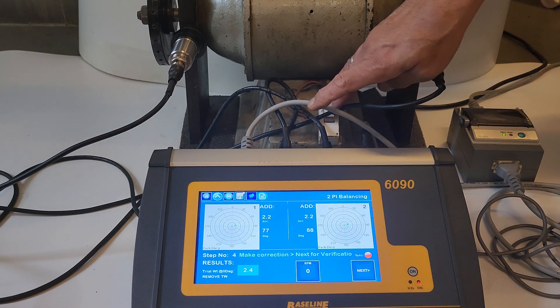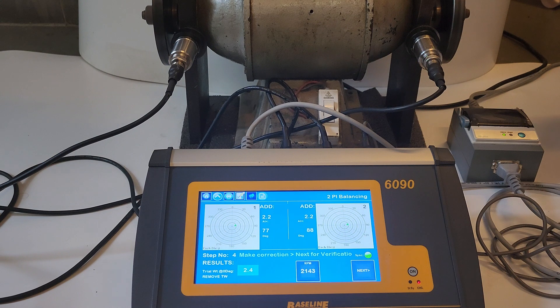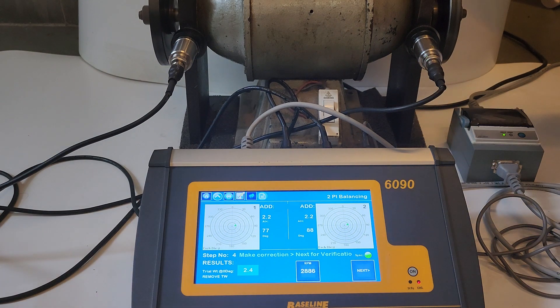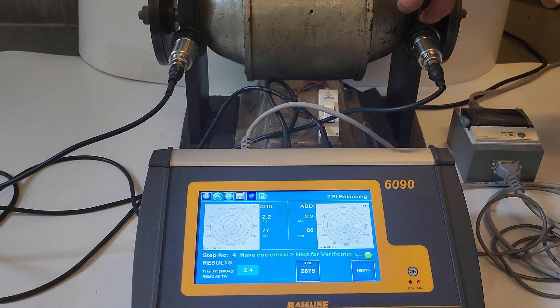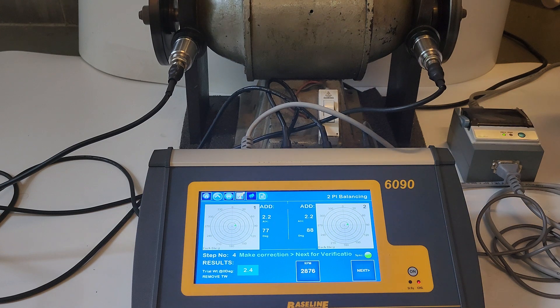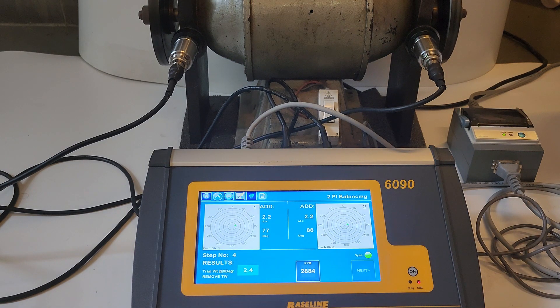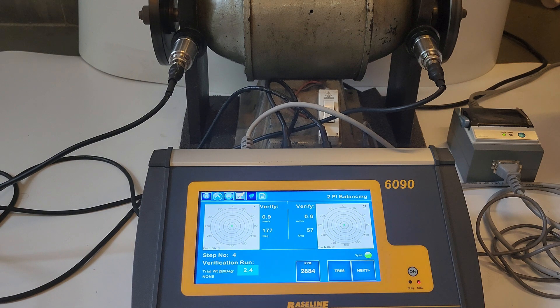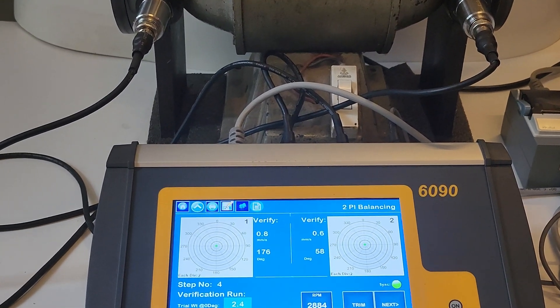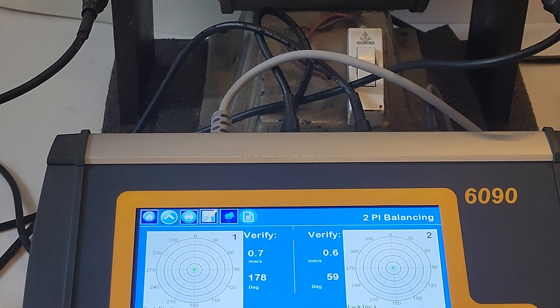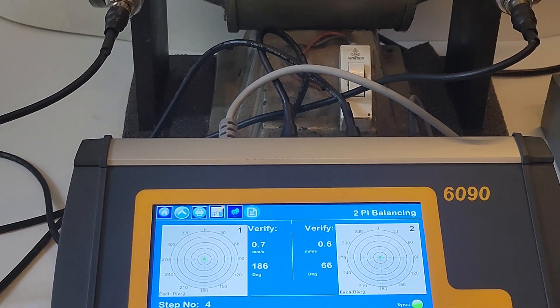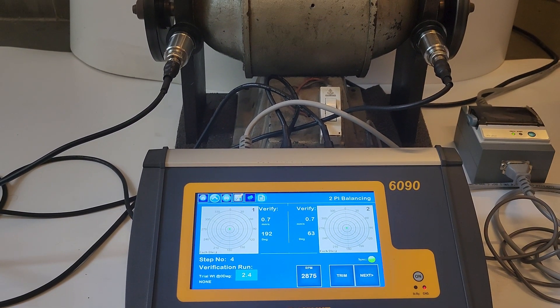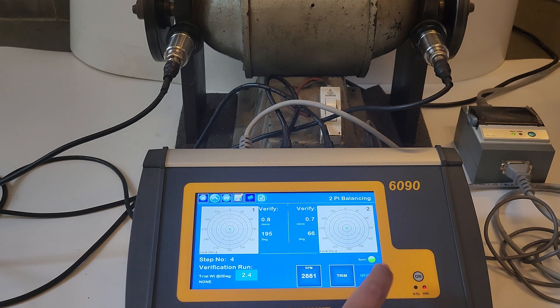After performing the correction, switch on the rotor then press next to see the final readings in the verification run and then stop the rotor. After this the user has an option to press the trim button to further reduce the unbalance. However, if satisfied with the readings, then the report can be printed and saved at this point by pressing the next button. As always, the report can be found from the file option on the home page and in the machine and location as saved by the user.